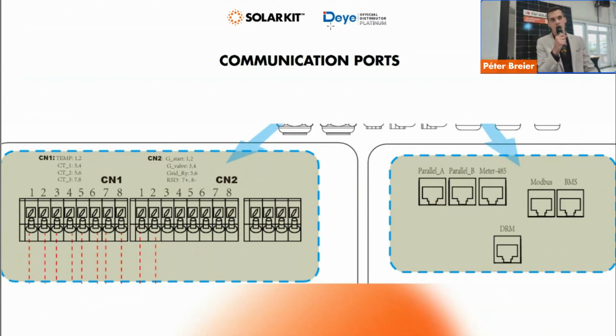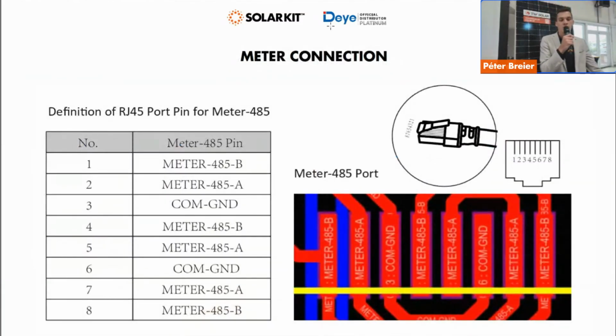Other than that, you can see the meter port. You have to use that one if you choose to install the system with a smart meter instead of the CTs. You can use Eastron or you can use Chint. In both cases, you have to connect there. And there is a very important appendix at the end of the user manual, which describes how this port is pinned. This is really important, because the high voltage Deye and the low voltage Deye have some differences in the pin distribution.